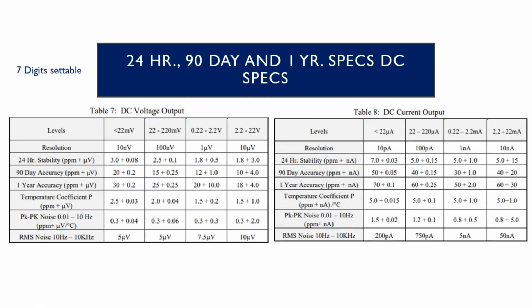Okay, here's our DC output voltages in more detail, both for voltage and for current. You can see, for instance, we have a 22 millivolt range with 10 nanovolt resolution, so we get pretty good. On the current, we have a 22 microamp range, and it's got 10 picoamp resolution.